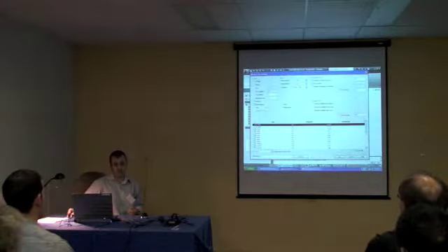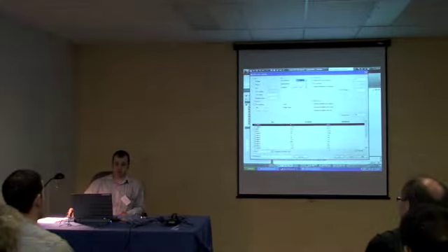Now again, at this point I can go and change that. And this is one of the items I mentioned earlier, the green design. Okay, so if I need to improve the current carrying capability of this wire, I can choose a different wire, 12 gauge or 10 gauge. Or I can look at square millimetres. So at the moment it's set at 1.5 square millimetres, it's only using 47% of the current carrying capability of the wire.